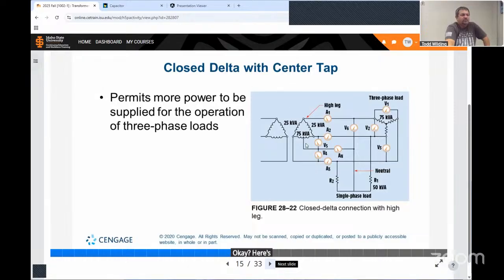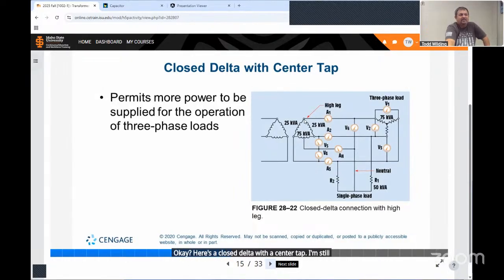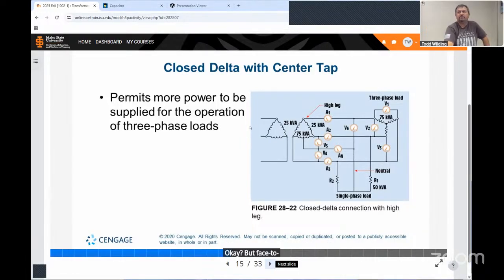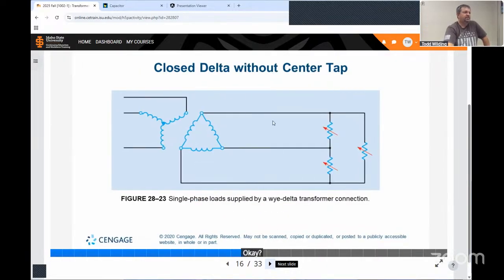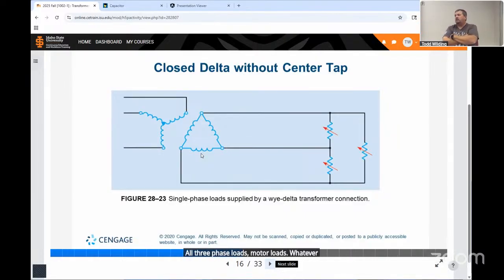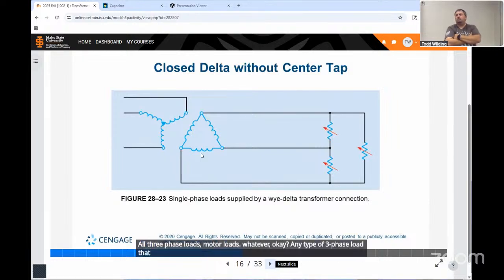Here's a closed delta with a center tap. I'm still going to have that high leg there because between that leg and that neutral is going to be a higher voltage than if I go this phase to neutral and this phase to neutral. But phase to phase, I've still got the same volts. Closed delta without a center tap. Where would I use a closed delta without a center tap? Why would I not need a center tap or neutral connection there? All three phase loads, motor loads, whatever. Any type of three-phase load that does not need a neutral, I do not need a center tap on that delta.